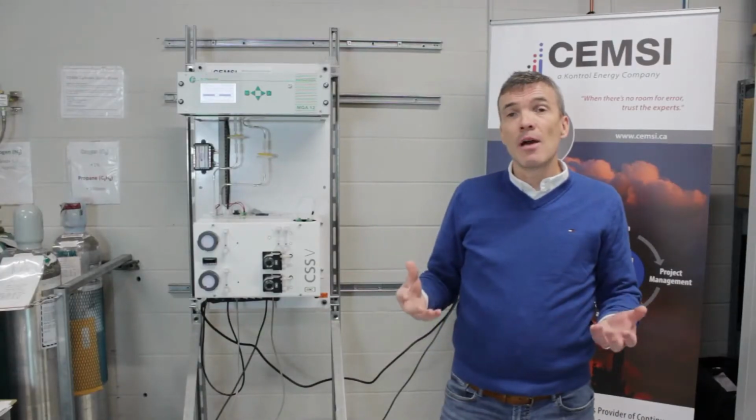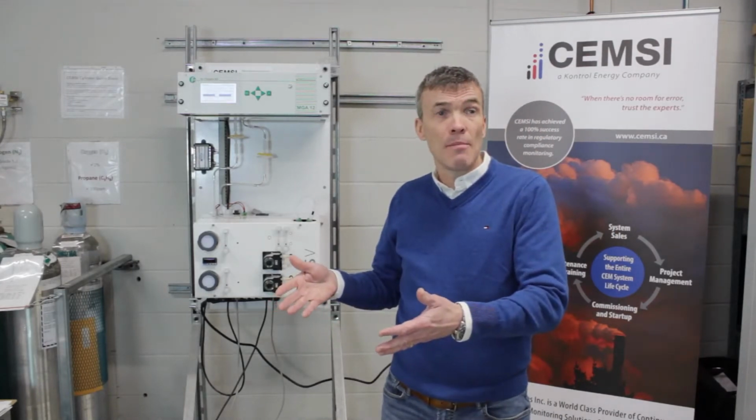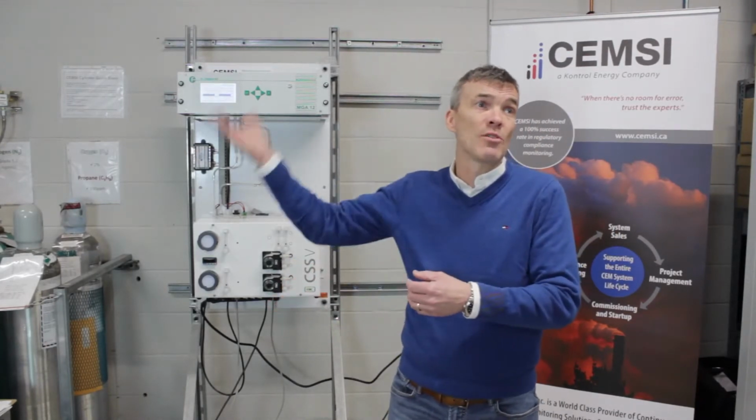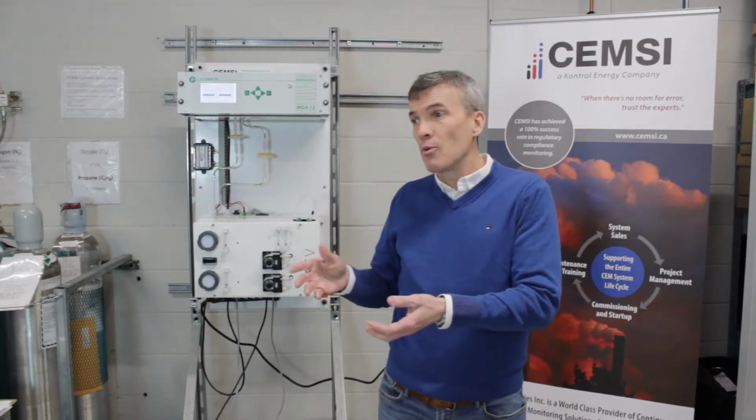That's why in a lot of these sample systems, we can have issues in the pump where we have it nowhere else. And people will say, oh my goodness, I'm not filtering things properly at the probe. My pump's getting all plugged up. And really what it is, is that chemical salt forming. Why would it form in the pump? Why? What's magical about the pump? It's the chemistry behind all this.